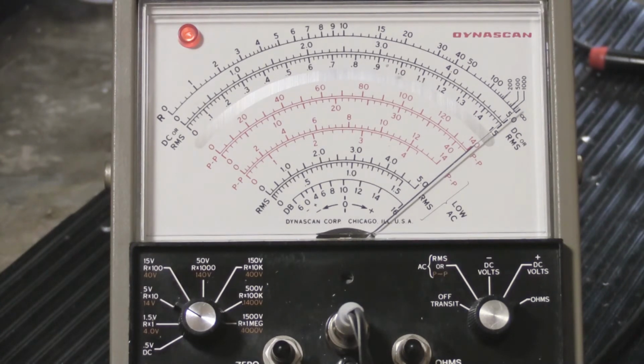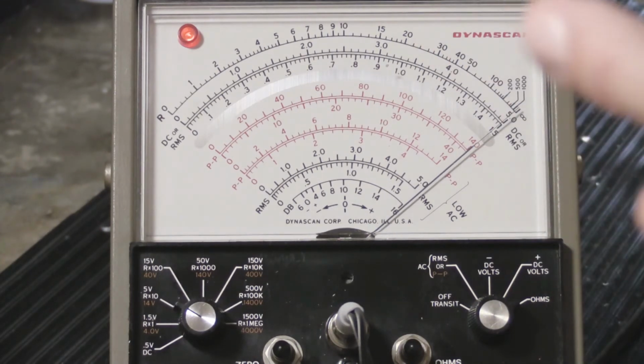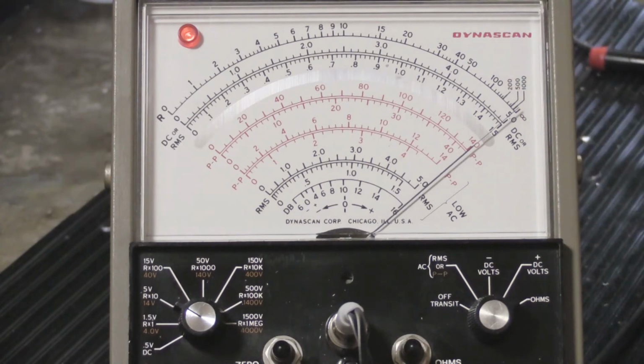So what you're doing is often referred to as either peaking up a signal or nulling out a signal. Peaking is setting it at its highest possible level, and nulling is setting it to its lowest possible level, or sometimes you'll be somewhere in between those. On a meter like this, it makes it a lot easier to see. I have sort of an example set up down here on the workbench that you can't see. I'm going to connect the meter to my little working example to show you how that goes.